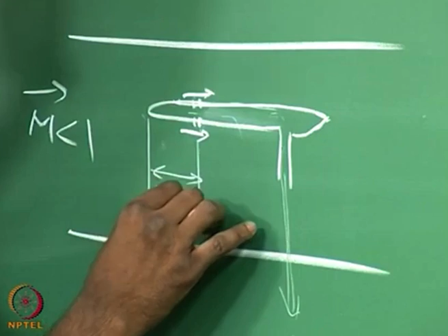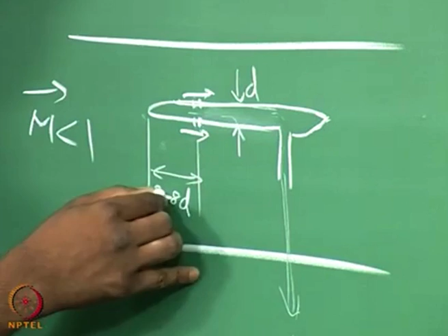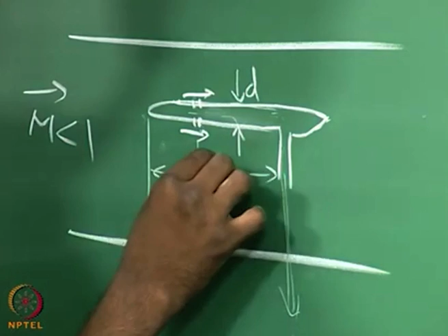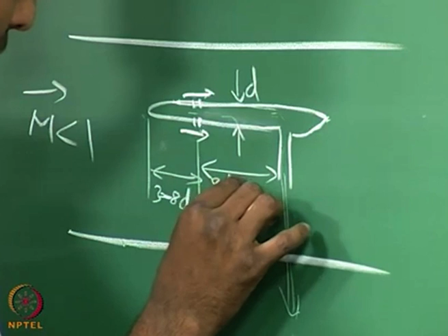What if I have a probe that is very short from the front to the hole? Let us say a hole center to the front, typical numbers people use are 3 to 8 times the diameter of this. If this is my D, then this is going to be 3 to 8 D, not 3.8. And the other distance, the holder to the hole position, of the order of 8D to 20D, 8 to 20 times the diameter of this tube, that is what we will use there. Why do we have to worry about this?